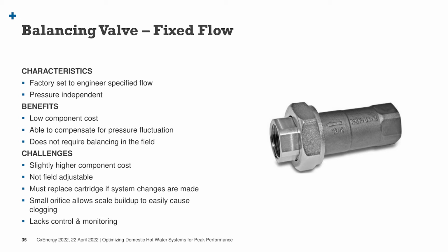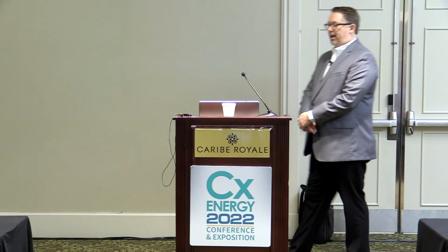Fixed flow, so these are your pressure independent balancing valves. They have cartridges that dynamically adjust to maintain that flow based on the pressure differential across that valve. The engineer specifies that they want half a GPM, 1 GPM, whatever, and it comes factory set for that. Some of the challenges there: it's got a small orifice that could potentially scale up, making that valve inoperable.